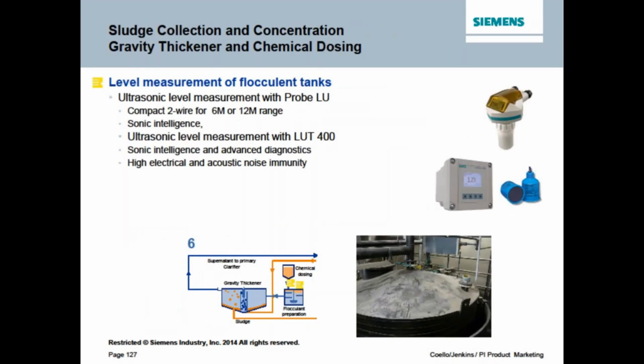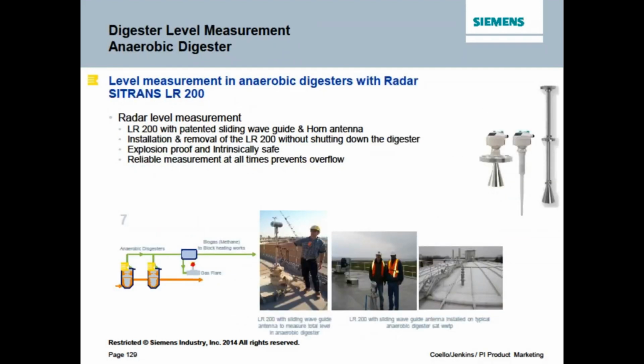If we look at sludge collection in a gravity thickener or chemical dosing, these are typically pretty straightforward, simple applications for ultrasonic, where we're not dealing with too many challenges as it relates to foam or anything else that we've talked about. So from an economical standpoint and an ease of use standpoint, ultrasonic probably makes the most sense in these applications. Within water, wastewater, when you start to deal with digesters, this is probably the one application that is a slam dunk radar application. There's always large amounts of foam in digesters. We're talking a few feet of foam, and they're typically very large tanks, wide in diameter.